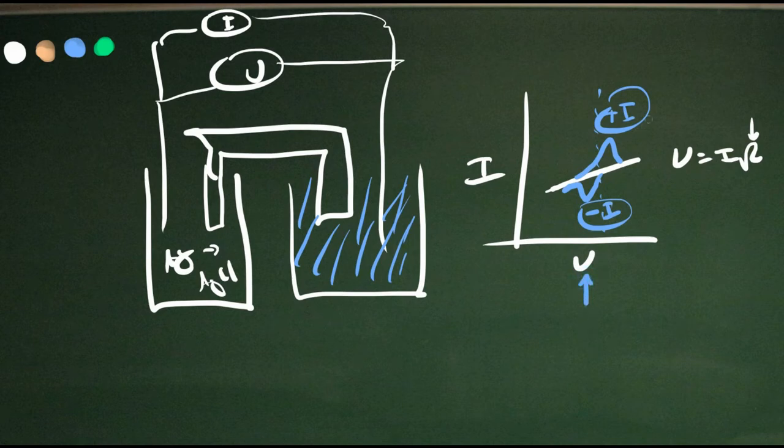For practical reasons, this is usually accomplished with a three-electrode system, not a two-electrode system, but I think it gets the point across more easily with two. You can do a cyclic voltammetry experiment, usually on small chemical systems, to characterize them and get some idea of what voltages they respond to. But you can use the same instrument to do larger scale experiments — controlled voltage reactions over time — during which you can monitor the current. It should be programmable to do a controlled potential discharge, a controlled current discharge, or vice versa — charging and monitoring battery charging as well. Neat capability for a really affordable price relative to what most of these instruments cost.